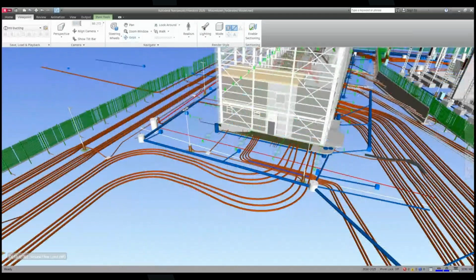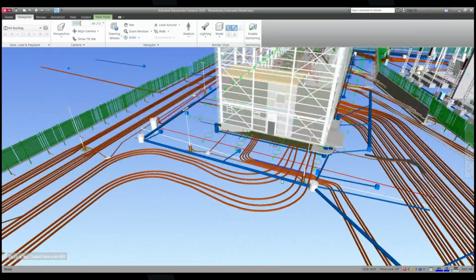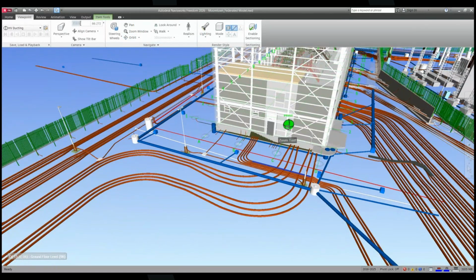At the GIS compound, the design mainly focused on the high voltage ducting connections into the substation building. The primary challenge was aligning the duct spacing, depths, and routing with electrical design requirements, particularly cable rating assumptions and installation constraints, while interfacing with the building structure. This required close collaboration with the electrical designers to ensure the civil layout supported the performance required of these cables.